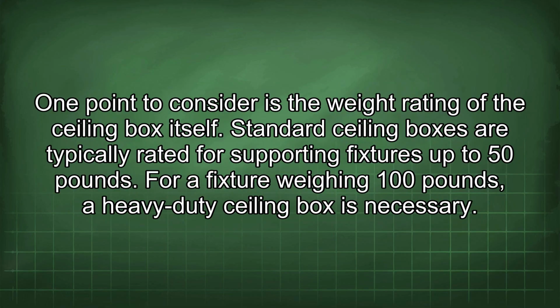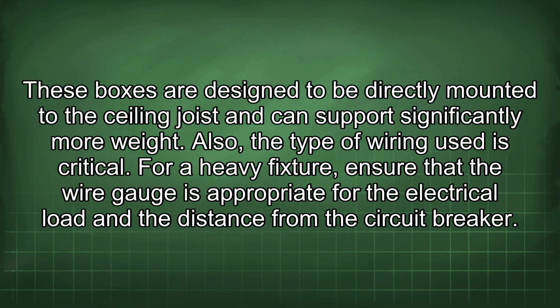One point to consider is the weight rating of the ceiling box itself. Standard ceiling boxes are typically rated for supporting fixtures up to 50 pounds. For a fixture weighing 100 pounds, a heavy-duty ceiling box is necessary. These boxes are designed to be directly mounted to the ceiling joist and can support significantly more weight.